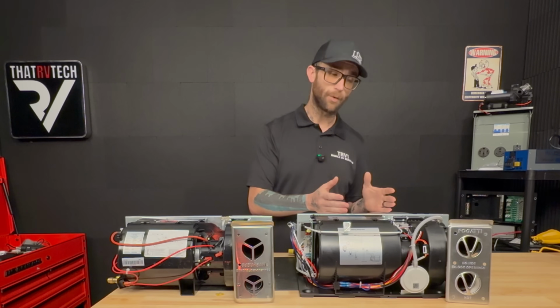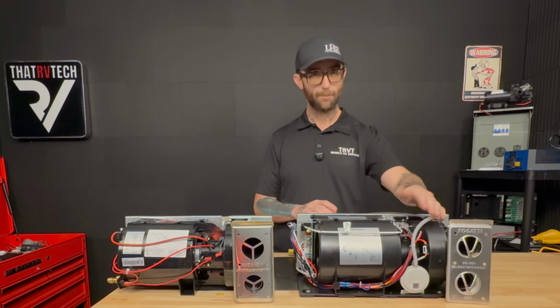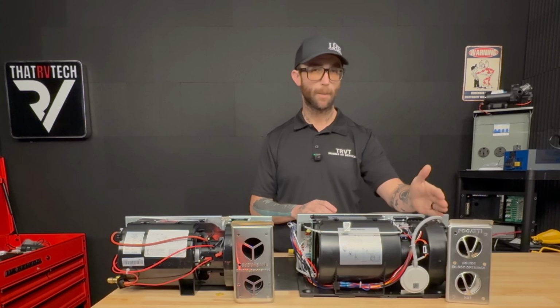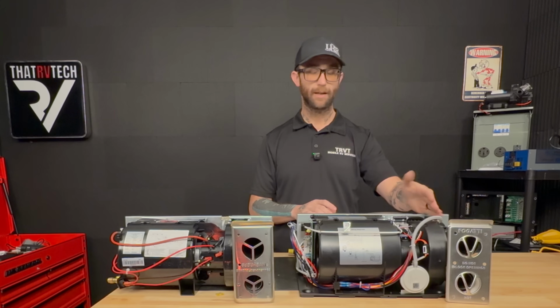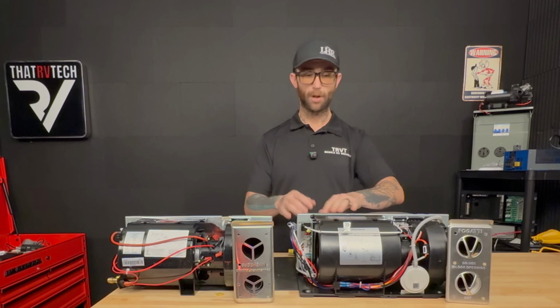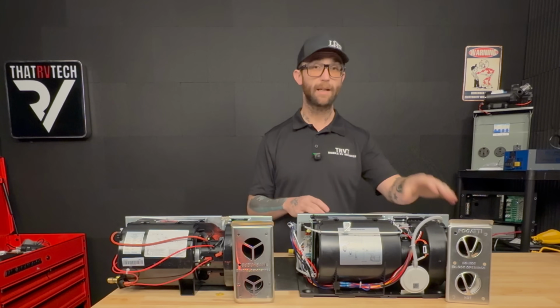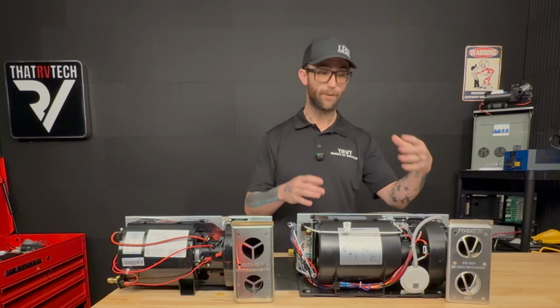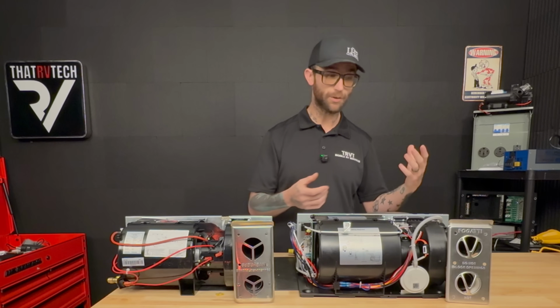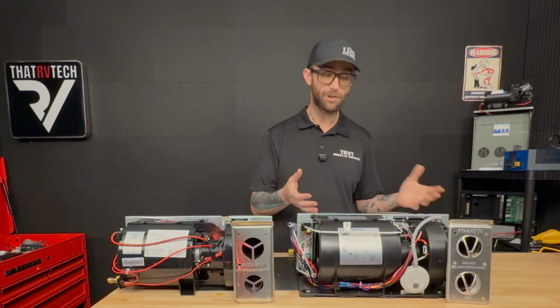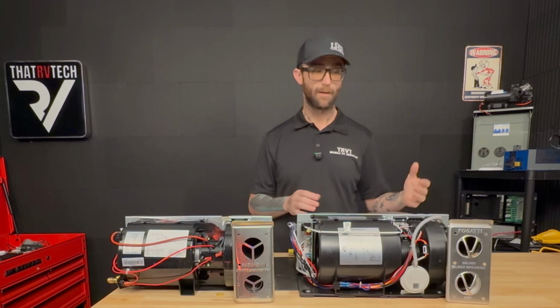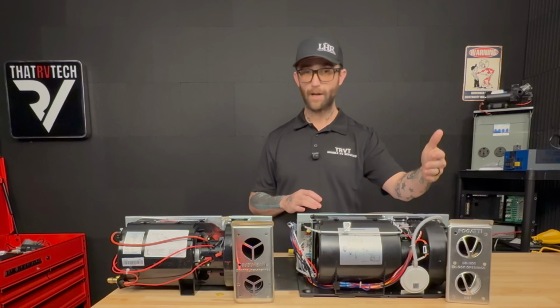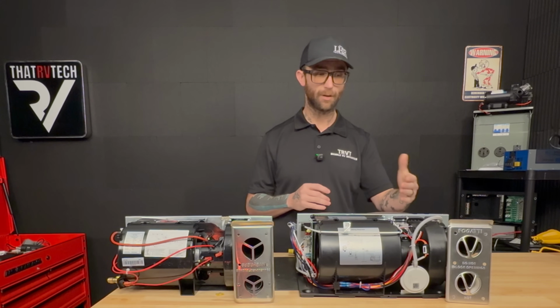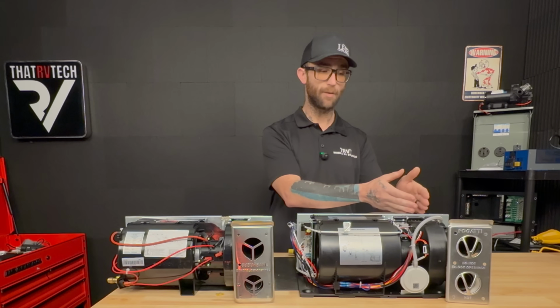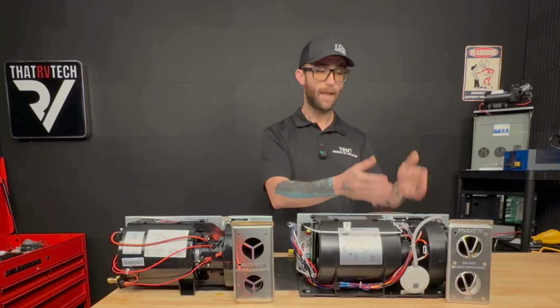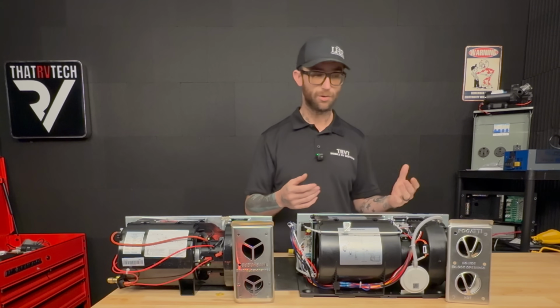Now we look over here at the Fogatti, and they're using that pressure switch again, but they're running it to the combustion side. Meaning, it doesn't care if there's airflow over here blowing the warm air off the heat exchanger. It cares if there's a flame with no circulation, in other words, overheating the heat exchanger or potentially causing a fire. This is not only going to be more accurate, more reliable, it's going to be safer. They're checking the correct side of the furnace for airflow, and they're also eliminating the issues with it.